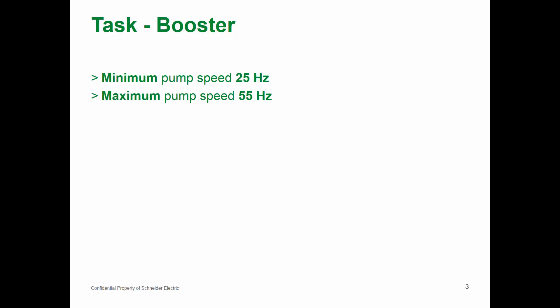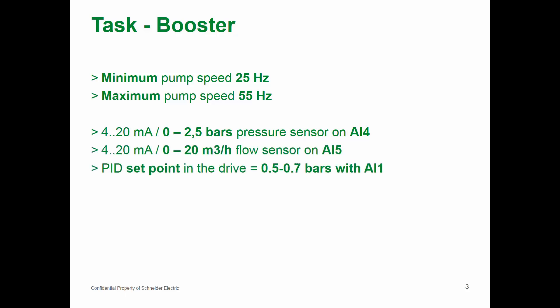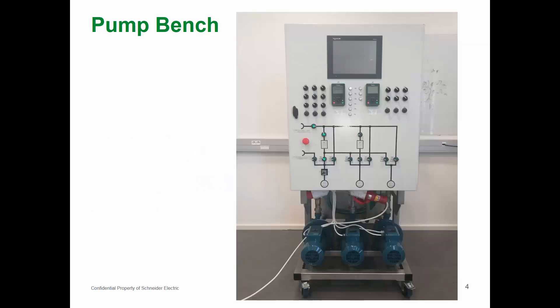For our task, first we need to set up parameters of our pump — minimum and maximum speed: 25 Hz minimum and 55 Hz maximum. After that we set up our sensors: we have a pressure sensor and a flow sensor. We need to set a PID setpoint — everything up to now is set by analog inputs. Then we set up auto/manual with a logical input, and we will use another analog input for speed setpoint in manual mode.